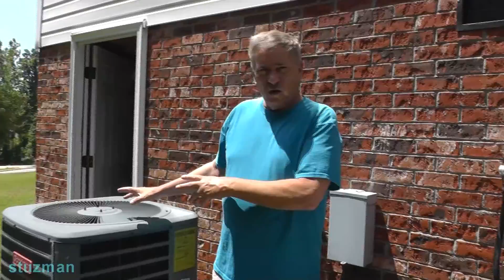So now let's go out to the outside unit and take a look at this capacitor. As you can see, the unit is off, but treat it like it is hot, because you may have a problem with one of the windings being open, the capacitor could be an issue, or your disconnect could have an issue. So even though it's off, treat it like it's hot.